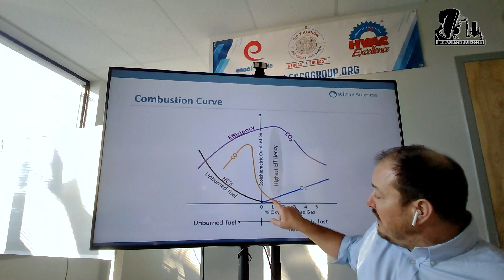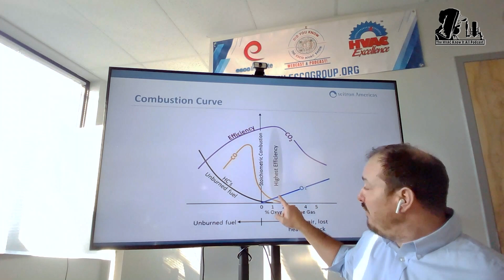The other reason why we look at this is because, let's say you're doing natural gas or propane, right? When you make it super simplistic, when you make adjustments to the fuel, pretend you're a dot on this little oxygen line. If I increase the fuel, what does my oxygen do? Decreases. If I decrease the fuel, you increase the oxygen. And what you're doing when you make that adjustment is to land the plane where the manufacturer wants, where my CO will be low, my oxygen will be a little bit, I'll have a little bit of excess, but that means I'll be running at my peak efficiency.